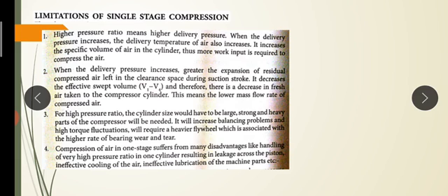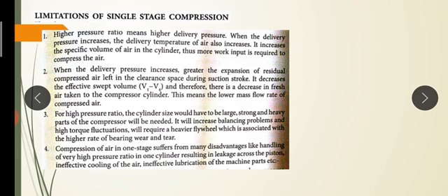A fourth limitation is that compression of air in one stage suffers from many disadvantages: handling a very high pressure ratio in one cylinder results in leakage across the piston, ineffective cooling of the air, and ineffective lubrication of the machine parts. These are the limitations of single-stage compression, and we can overcome them by using multi-stage compression, which we will discuss in this class.